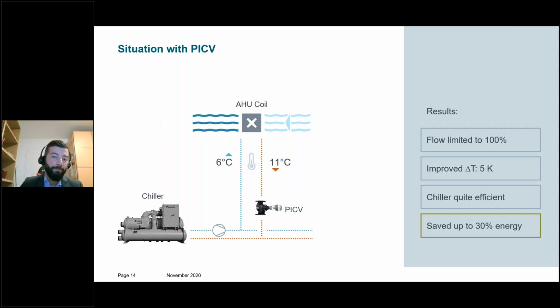Nevertheless, let me also mention that a PICV alone can never guarantee that your delta T is always going to be the highest, simply because a PICV can only control the flow and has no direct influence on the temperature. So for this, as we will see later, you need intelligent valves. But this improvement, moving from static to dynamic balancing, already saves up to 30% energy and preserves comfort.